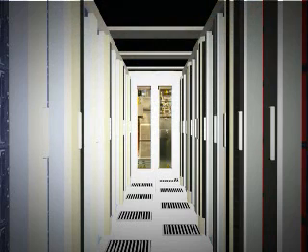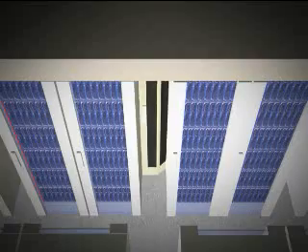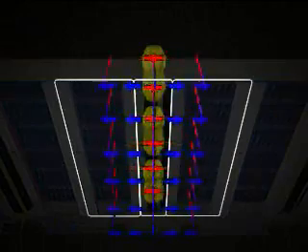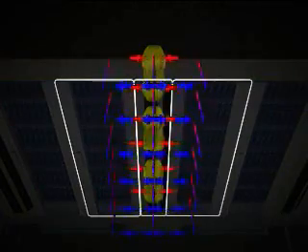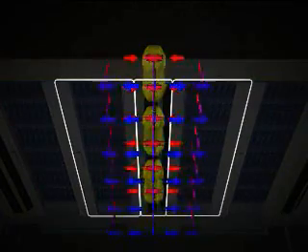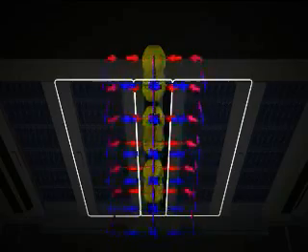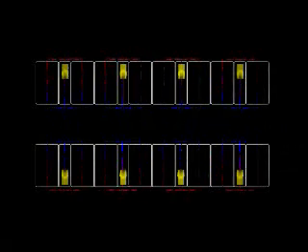Even in a site where there's no false floor, cold aisle containment shouldn't be ruled out. By introducing a liquid cooling package called LCP in-line, it effectively replaces the need for a CRAC system and provides up to 30 kilowatts of cooling per module. The LCP in-line still requires water as its cooling medium, and using an air-to-water heat exchanger, it blasts cold air into the cold aisle, where it's absorbed into the server inlets. To provide additional cooling capacity or even redundancy, it's simple to add additional LCP in-lines along the aisle, whenever and wherever you need them.